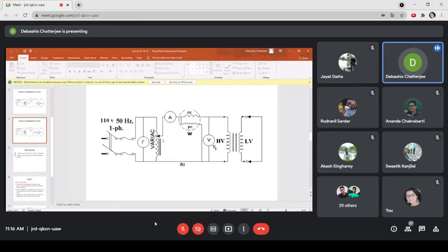Now if you take again that 100 volt to 500 volt, 1 kVA transformer, the voltage required, if you had connected the low voltage side at the test end, would be 8% of 100 volt, that means only 8 volt, right? And the current would be very low. So you see that the pressure coil rating should be of very low voltage, of the order of 10-15 volts, but the current rating should be large, because here the rated current in the high voltage side is 2 ampere.